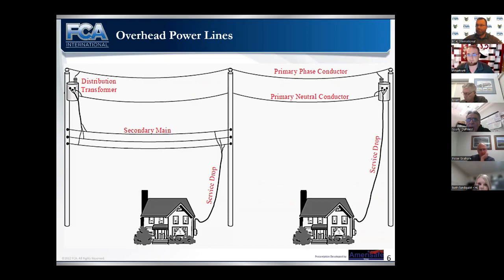So what you have here is a picture of overhead power lines. And what I wanted to do is discuss what we see on our standard jobs, with our regular distribution power lines - these are not the steel towers that are highly elevated, these are what you normally see on the side of a residential road. On top, we have our primary conductor and our neutral conductor, and we have a transformer. This steps that power down to a level that you can bring into a house or a facility. That goes to the secondary main, and then you generally see a service drop going to the facility or the house. Now, this service drop is what we come into contact with most. The secondary line may be right along where we're working, as may the primary conductor, but the higher up it is, the harder it is for us to touch.